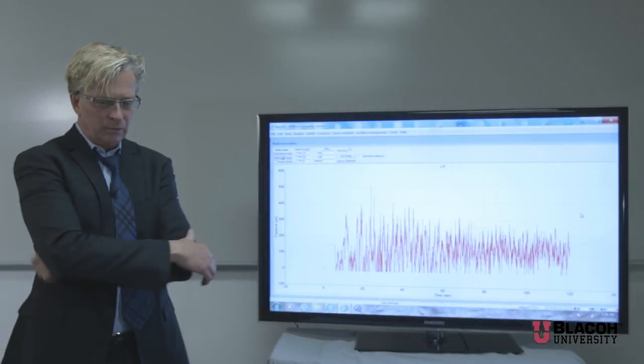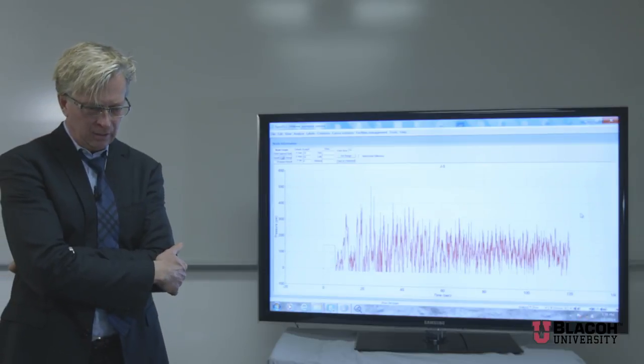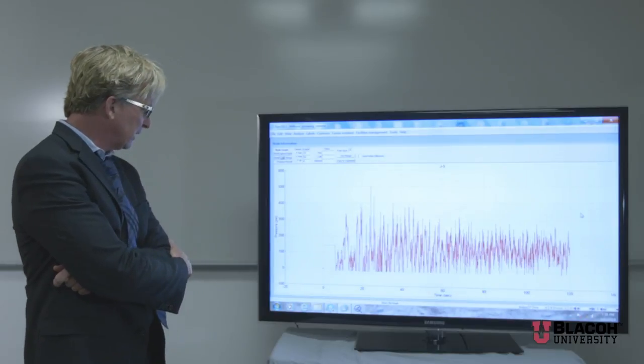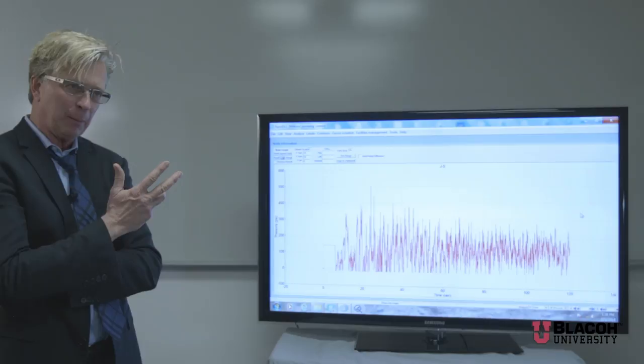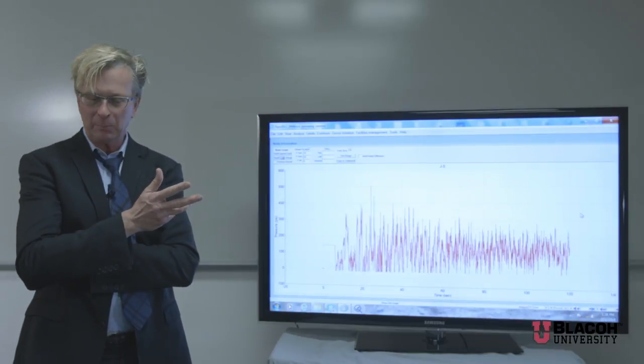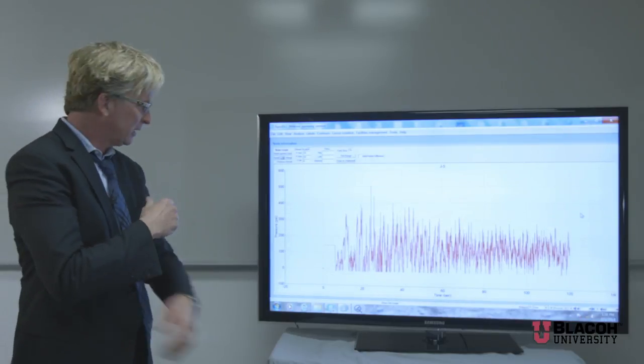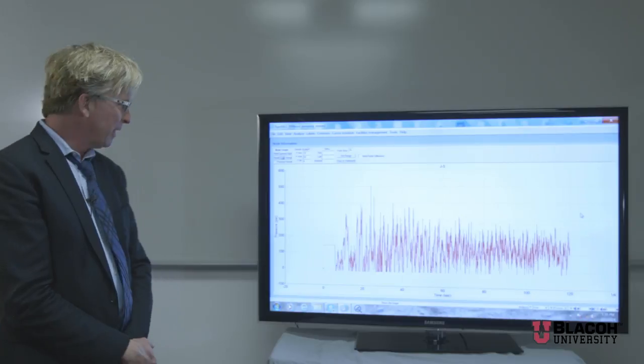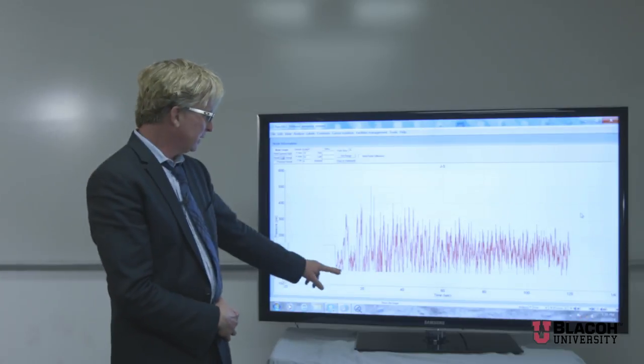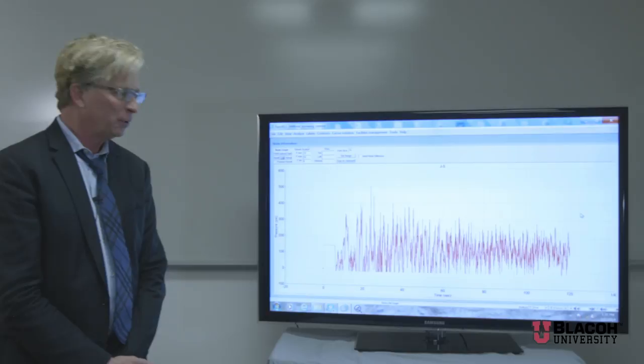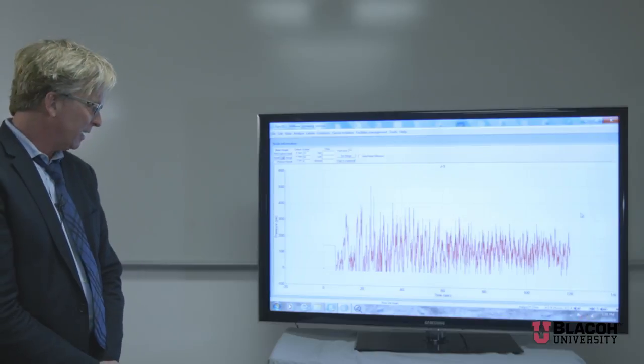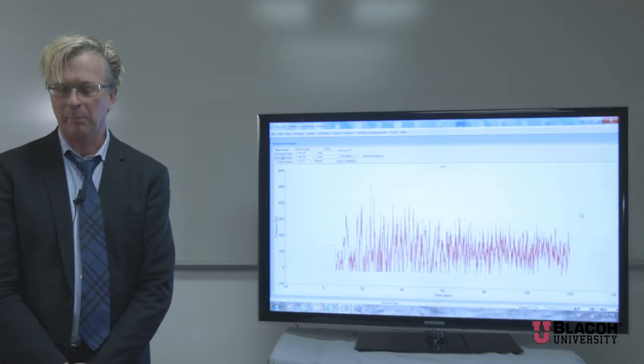With the three pumps in series, if we look at our steady state conditions, we're operating about 625 PSI, which means our pressure is going from 625 PSI to maybe 50 PSI, then that oscillates back up to almost 1200 PSI. Huge pressure difference. Let's take a look at a different node. As we're reaching towards the end of the tunnel, we see the pressure—our steady state condition was about 150 PSI. That negative pump trip dropped to 50 PSI at the pump. In this case we're dropping to a full vacuum. When we have that full vacuum, we're going from a vacuum tension to 500 PSI when we collapse that vapor pocket created through cavitation.